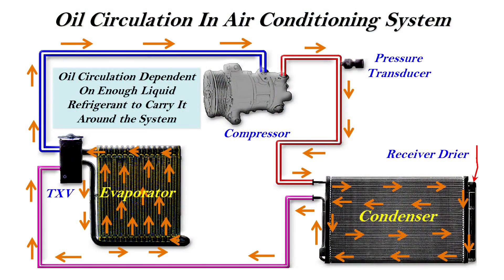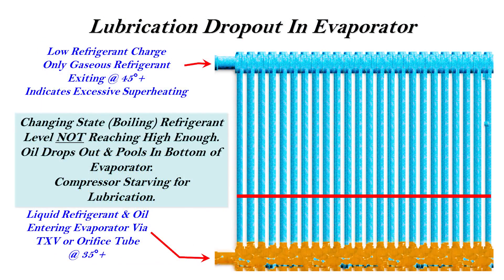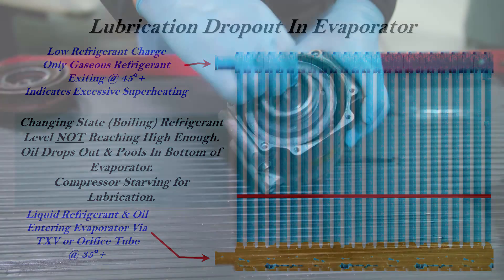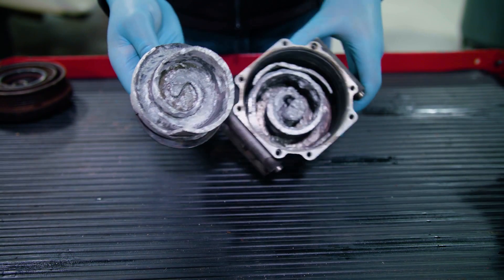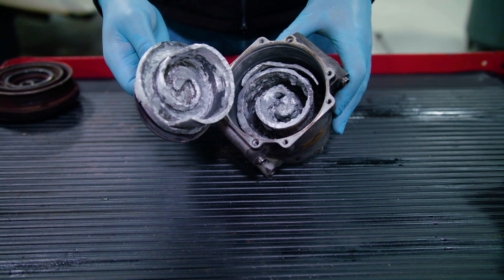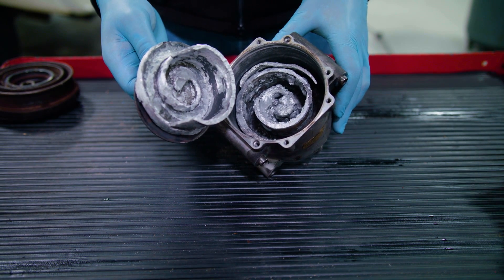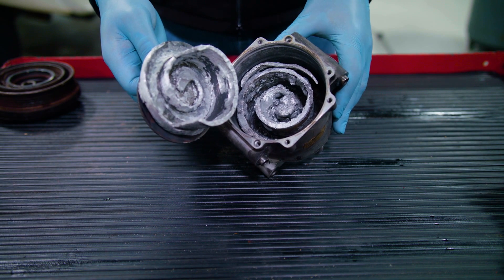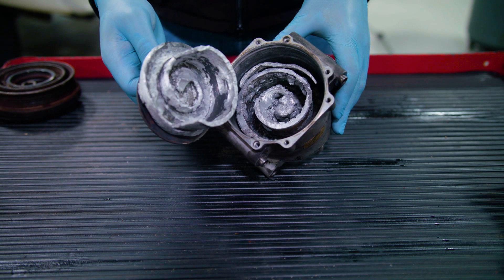Yet small leaks that result in a low charge over weeks or months can mean death for the compressor. Let's understand how this can happen. If the system develops an undercharge due to a leak, the oil, which does not evaporate, separates from the gaseous refrigerant and drops to the bottom of the evaporator. Now only pure refrigerant, which by itself is a powerful degreaser, returns to the compressor. This washes down the vital lubricating film of oil from the compressor moving parts. With no lubrication, the compressor starts to wear and fails rapidly. And so you can see how an undetected leak is often the root cause of a repeat compressor failure months after the original repair.